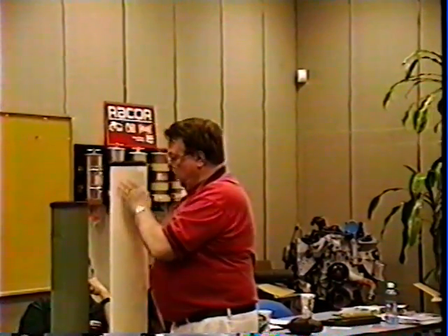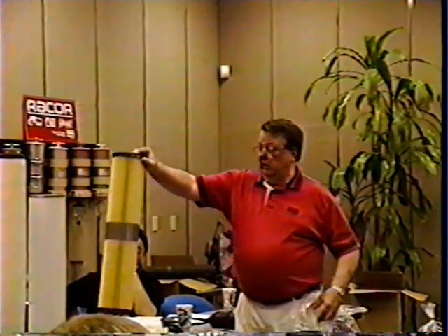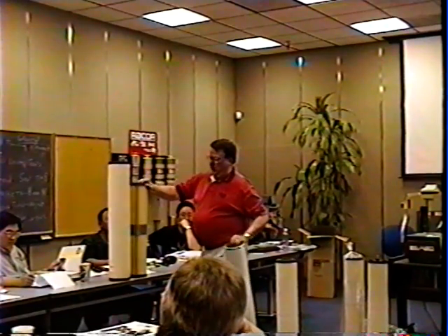Now, what we found out with all of our guys in Henrietta being jet fuel people, was that we have requests in the field that in some cases we want a synthetic separator, or in some cases we want an SP instead of Teflon. Teflon is expensive. In diesel fuel, in the reefers and the beefers and all those, we think that's a better combination rather than the Teflon. Then what we do is every change out, we change them both.